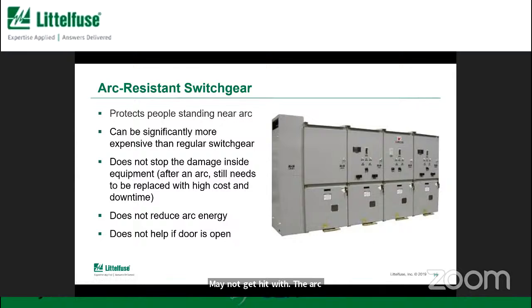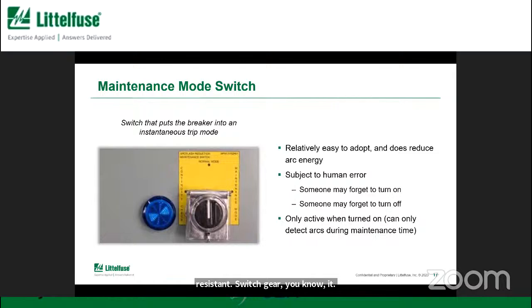So this does a really good job of making sure somebody who is standing here may not get hit with the arc flash. Now, this equipment, because it's built to be so much stronger, is quite expensive. Sometimes it's 2 or 3 times as much money as the regular switchgear. And although it might prevent somebody standing here from getting severely injured, it does not reduce the energy. So the equipment inside is still going to be heavily, heavily damaged, and there could be a high cost to replace it. And if somebody has the door open, doing something inside, then it really is not going to do its job, because the door is open. It can't block the energy inside. So arc resistant switchgear certainly can be good, but you have to understand that it does not reduce the energy and so does not reduce the damage that could occur inside.